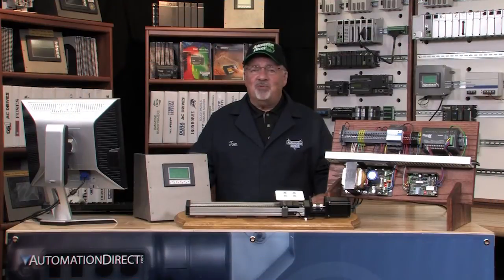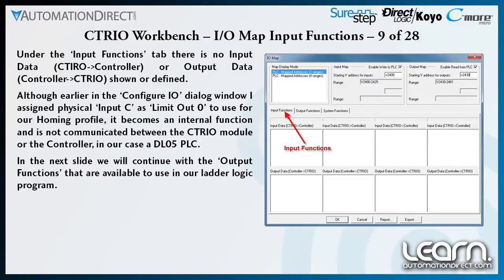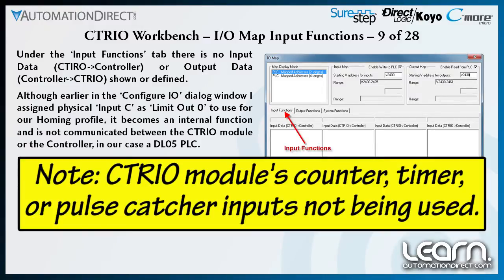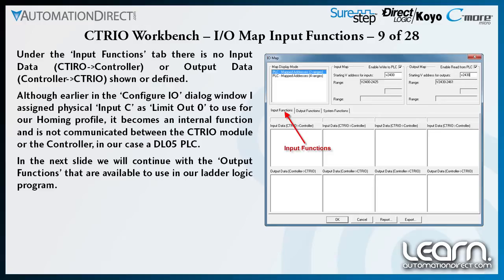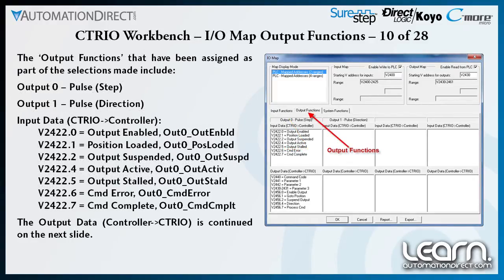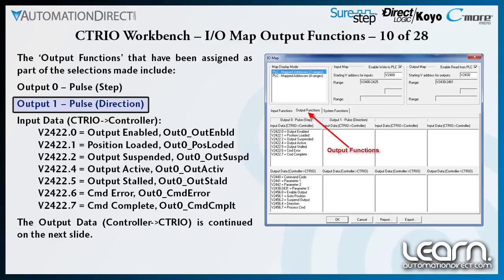Under the Input Functions tab, there are no input assignments for the CTRIO to controller data or outputs for the controller to CTRIO data. Earlier in the Configure I/O dialog window, I did assign physical input C as a limit out 0 to use for my homing profile. But it is an internal function and is not communicated between the CTRIO module and the DL05 PLC. The output functions assigned include output 0 pulse — providing steps to my stepper drive via connection terminal Y0 — and output 1 pulse, providing the directional signal via connection terminal Y1.